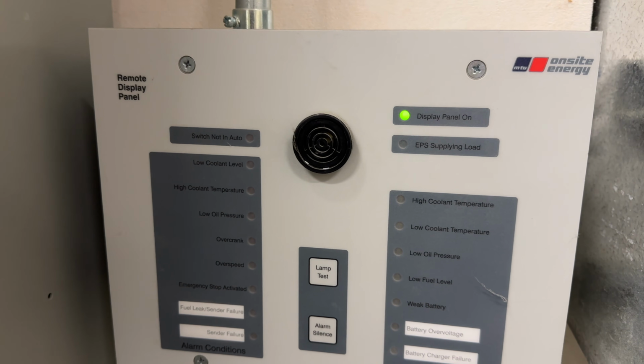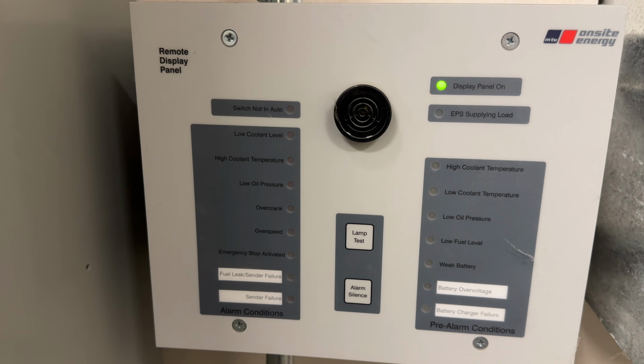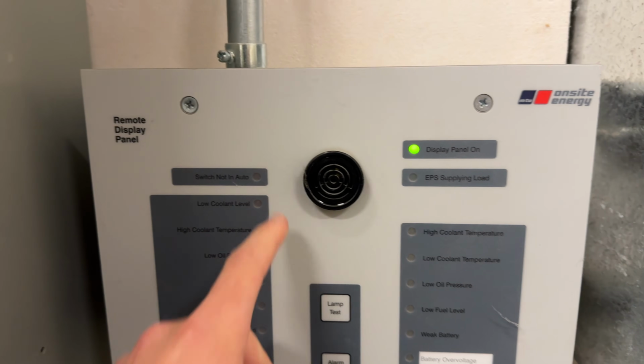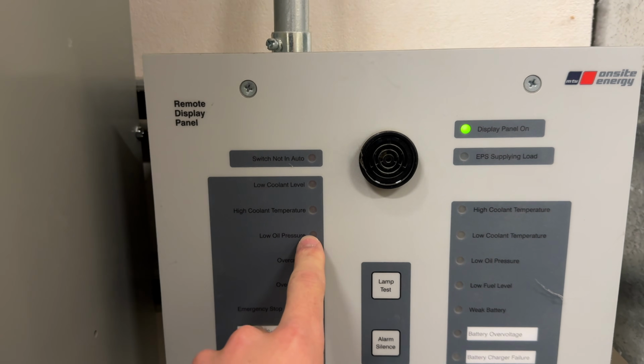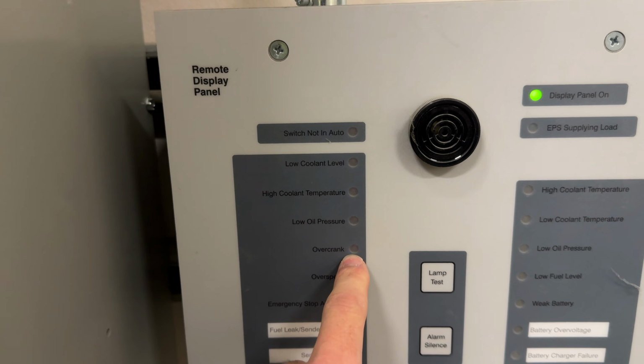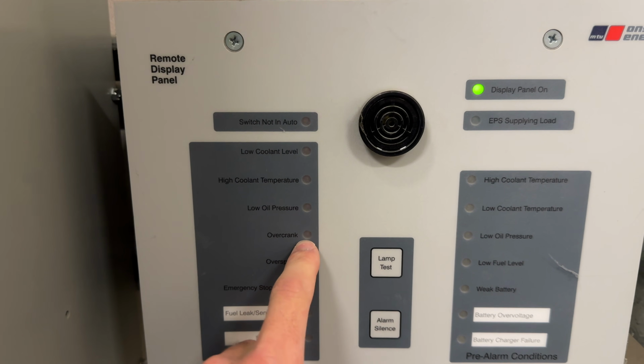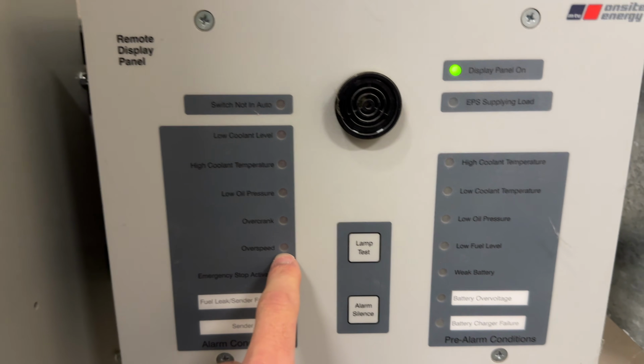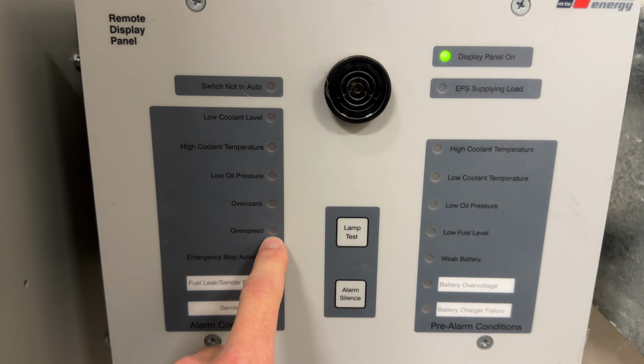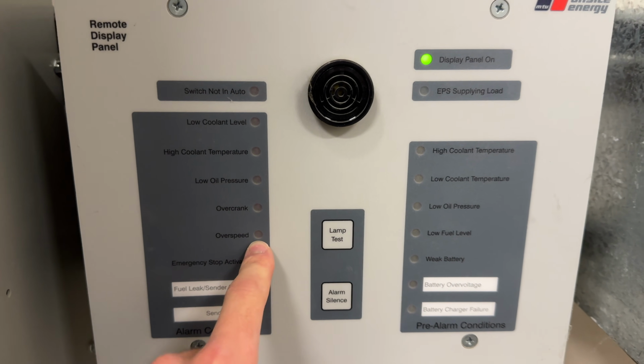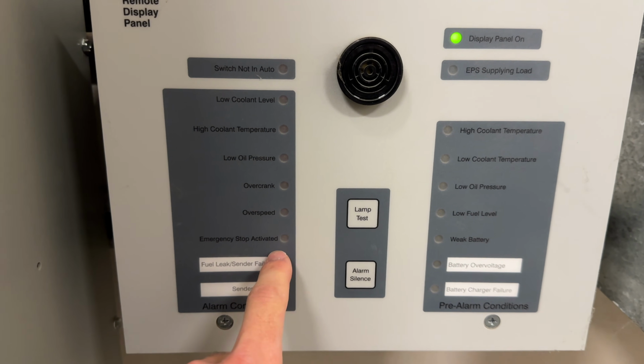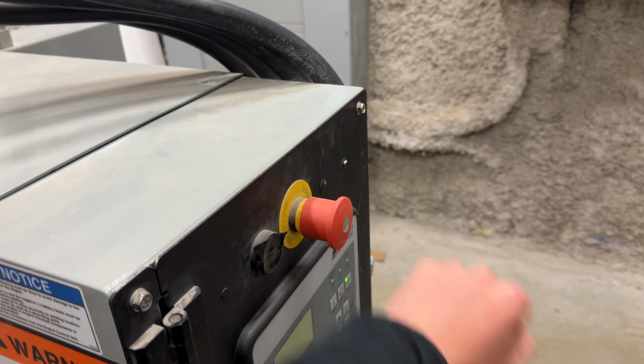This thing screams if there's any problems. So it'll show what issues there are with the generator. If low coolant temperature, high coolant temperature, low oil pressure, over crank, meaning that it's been cranking the engine over but the generator didn't start. Over speed, if the engine exceeds 1800 RPM by too much or 60 Hertz. Emergency stop activated. That would be if I hit this emergency stop button to shut the generator down. That would be active.